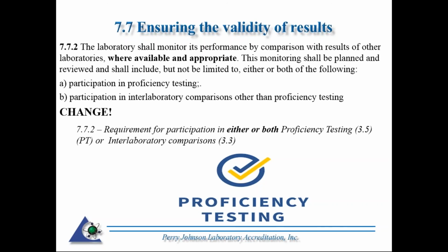This monitoring shall be planned, reviewed, but not limited to either or both of the following. So you have to either participate in proficiency testing, that is, through a third-party proficiency testing provider, or participate in an interlaboratory comparison. That would be both yourself and at least another laboratory facility where you're comparing your results in a meaningful way. And I don't want to go into too much here because this is what we already have in place in PL1.